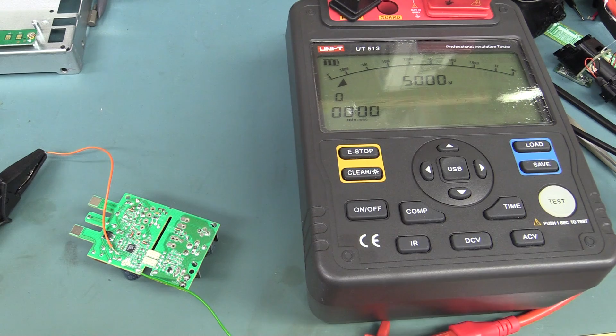What I've got here is my Uni-T UT513, a 5 kilovolt mega insulation tester. It only allows us to do basically 1000, 2500 or 5000 volts, but this will let us spark it over, and it's got a reasonable amount of energy behind it, so it should hopefully continue to spark, not just like a static discharge - for example when it builds up on yourself, it can get 20 kilovolts or so, but it's all over Red Rover once you discharge it. This thing should hopefully continue to spark this over.